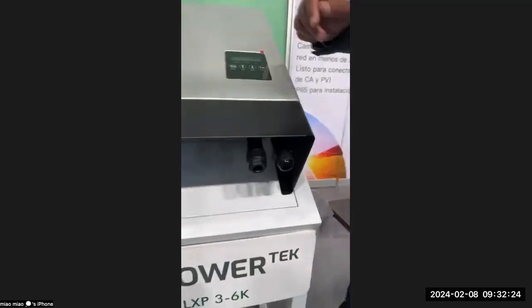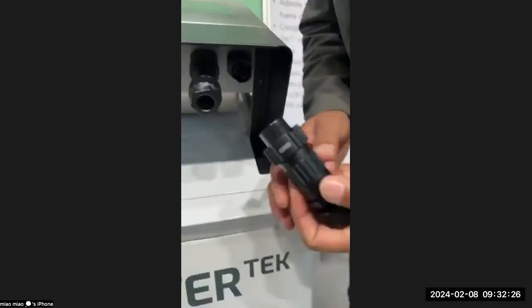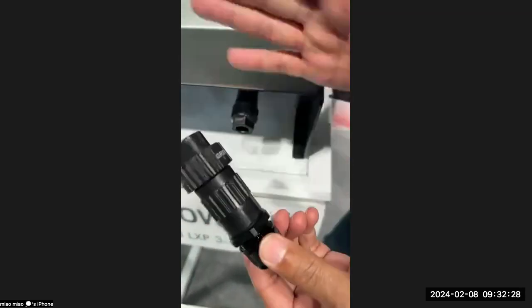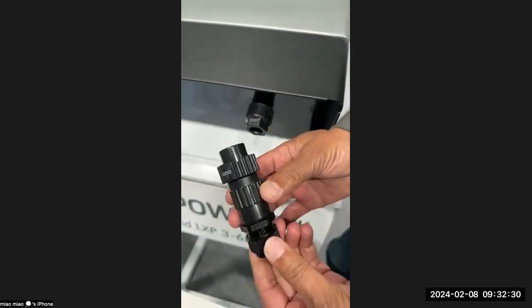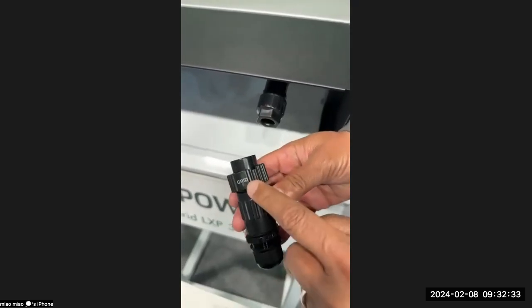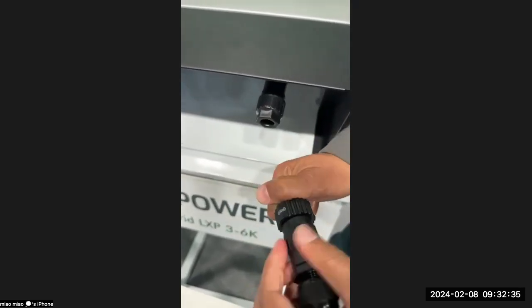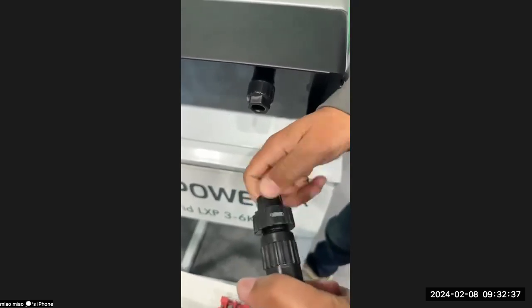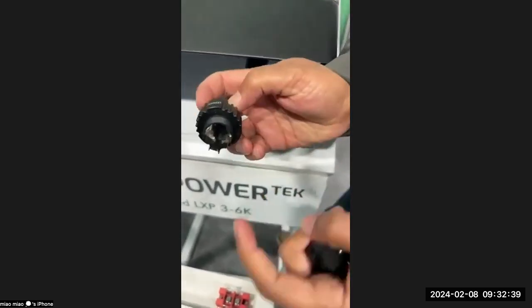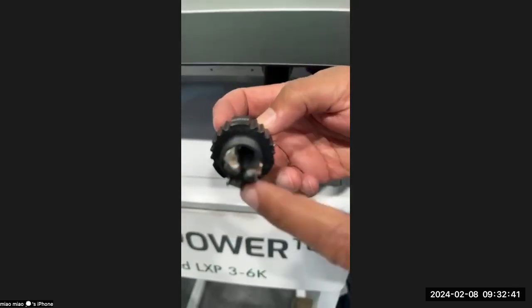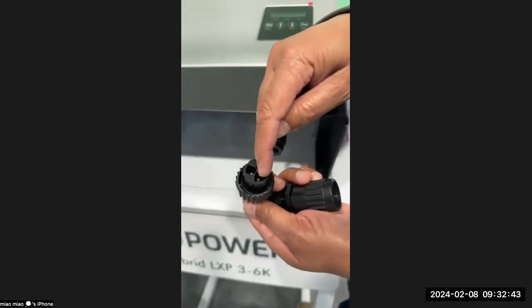Okay. So earlier on, we were talking about the plugs to wire up the LXP5. It's simple. It comes with a set of plugs in the box. One is marked the grid. You simply open it up here and you do your house wiring straight into here. So you've got your live, your neutral, and earth. It is marked on the top where to go.